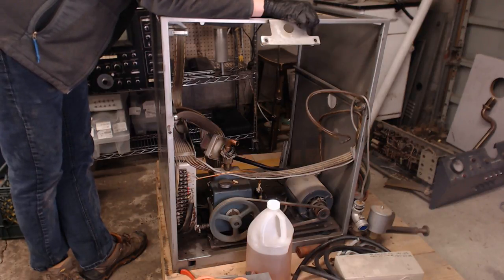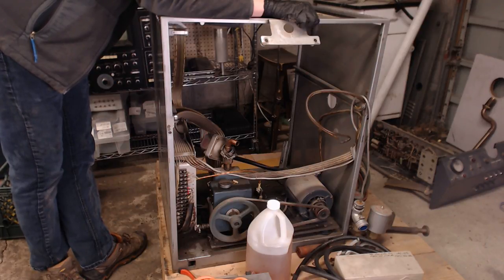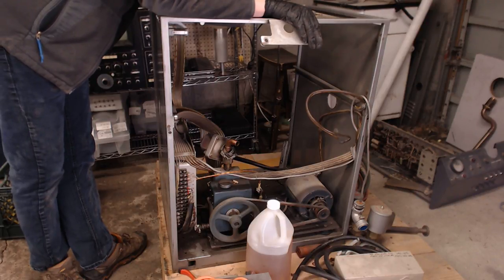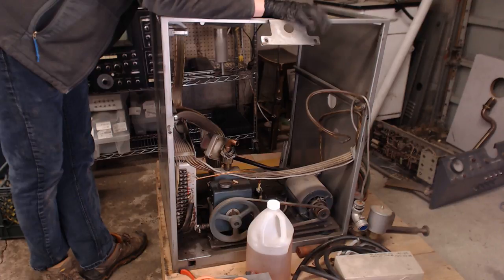Now, this roughing pump's basically got these chambers on the inside that change volume. It expands the volume, closes off a valve, sort of, and then decreases the volume to expel all that air, but that doesn't work at high vacuum. So you use both these pumps, but getting this roughing pump out of this particular unit is quite challenging because it's mounted on these vibrational isolators. And vibrational isolators have got an encased nut inside of them, or captive nut. The problem is that this captive nut spins because the rubber's old. So it's really, really hard just to take the screws out of the isolating feet.